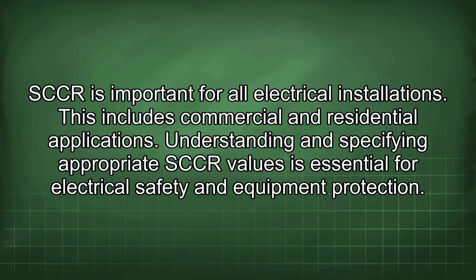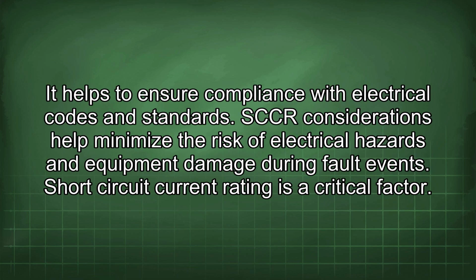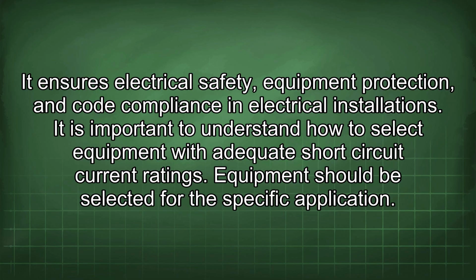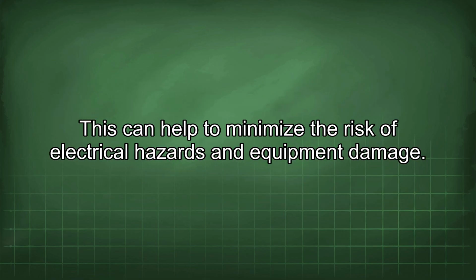Understanding and specifying appropriate SCCR values is essential for electrical safety and equipment protection. It helps to ensure compliance with electrical codes and standards. SCCR considerations help minimize the risk of electrical hazards and equipment damage during fault events. Short circuit current rating is a critical factor. It ensures electrical safety, equipment protection, and code compliance in electrical installations. It is important to understand how to select equipment with adequate short circuit current ratings. Equipment should be selected for the specific application. This can help to minimize the risk of electrical hazards and equipment damage.